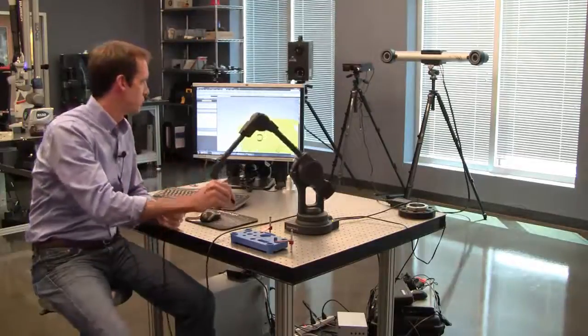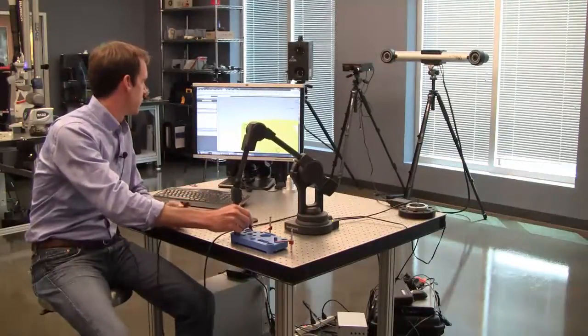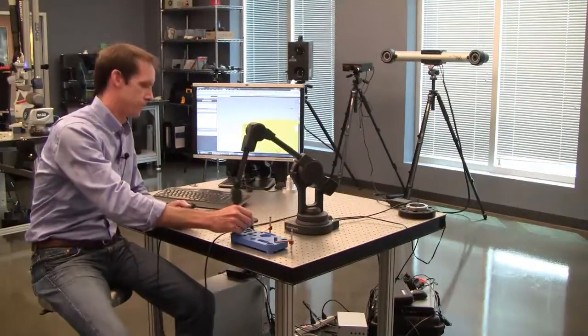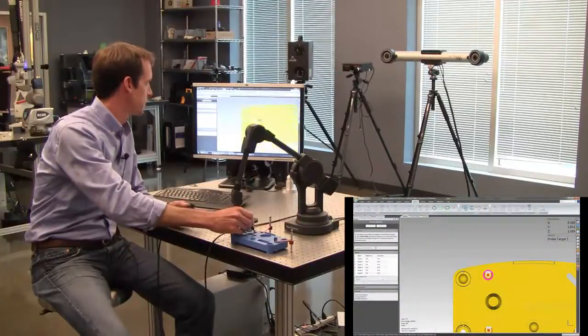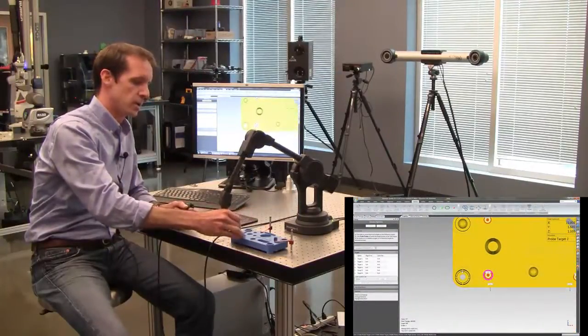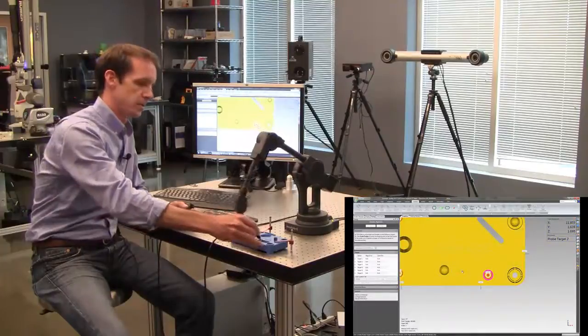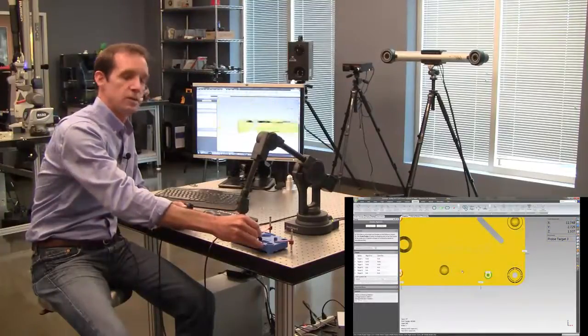And what we'll do is we'll take points. You can see as we move the device, you can collect points. As we collect them, just like all the other articulated arm devices, we collect the input at the center of the probe.